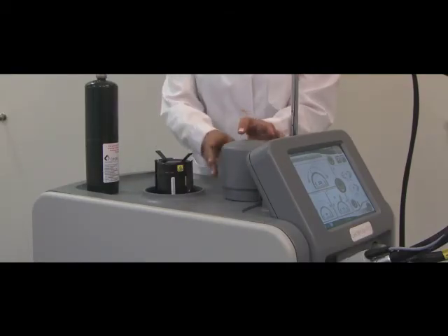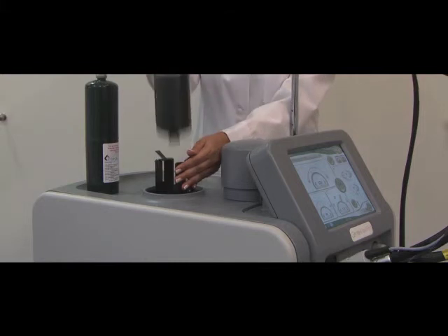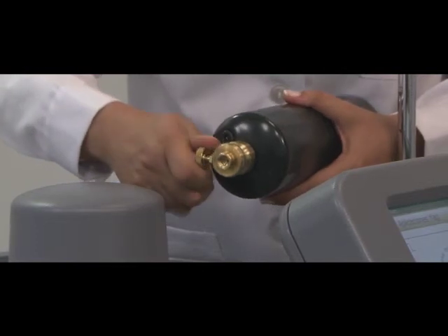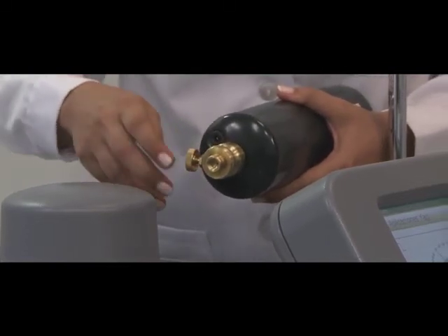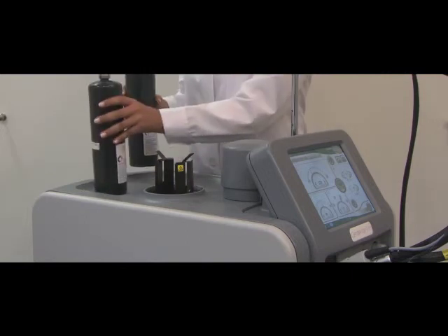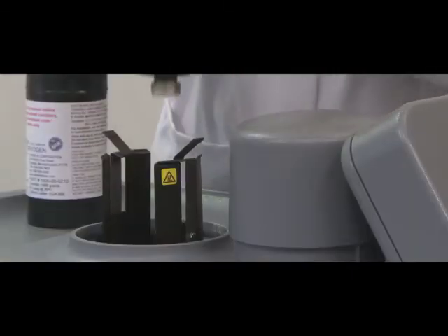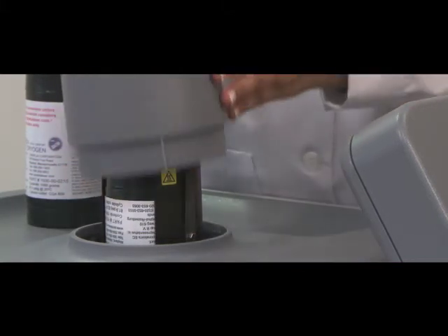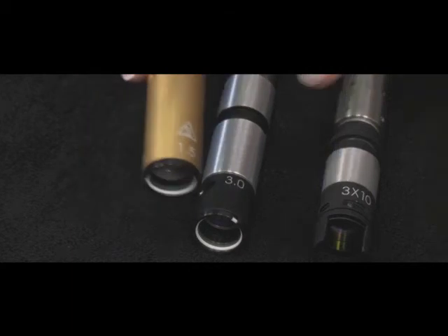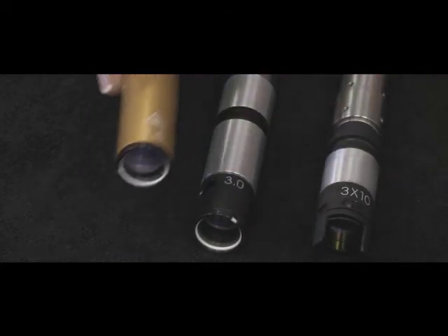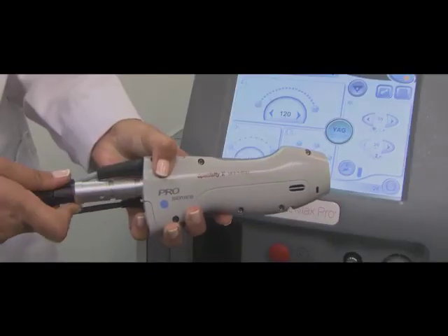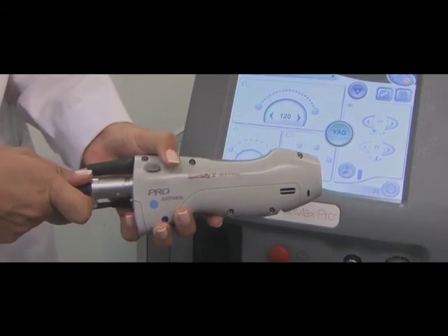To change the Cryogen container, separate the clips and remove the container. Empty the container with the Cryogen key before disposing of it appropriately. A new container can be kept ready near the device, taking advantage of the warmth emitted by the device. Never actively heat the container in warm water or by any other means. Note that for the specialty delivery system there are 3 spot sizes, the 1.5 mm, 3 mm, and the elliptical 3 by 10 mm. The spot size is chosen by moving the slider along the handpiece.